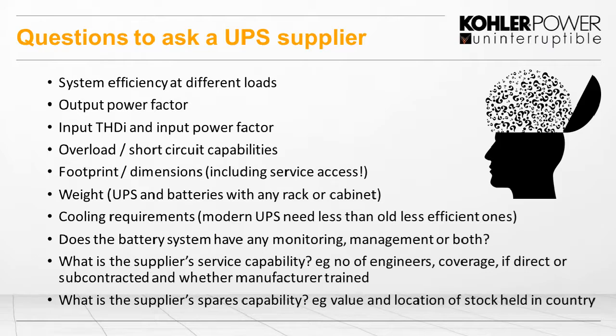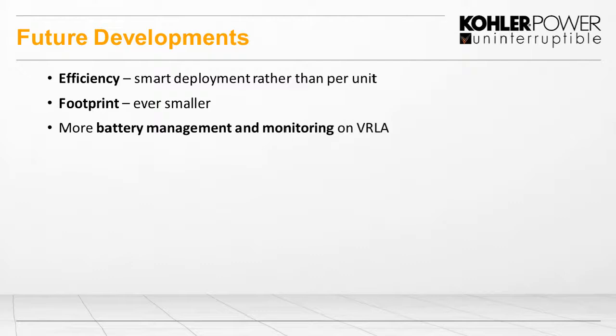So we carry on now to what we see as some of the future developments. We see efficiency as one of the areas where people are concentrating. So we're looking at smart deployment of the energy use, and that can be either with the modular or with what we call extra VFI, only allowing the required modules to run when required. We always get asked for an ever smaller UPS, so we're seeing smaller and smaller UPSs coming in. We also believe we're looking at more battery management and monitoring on the VRLA, the lead acid battery. It's a relatively modern thing to be putting on batteries in the last few years, and we're seeing that it's increasing the reliability and resilience of the battery itself.